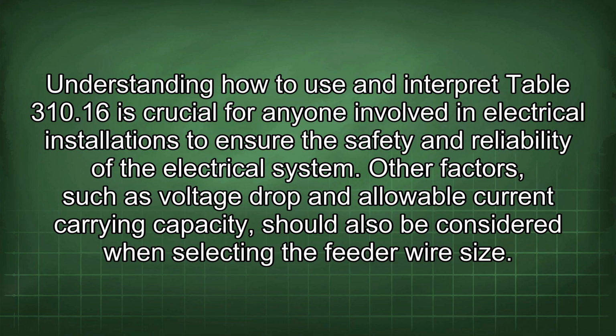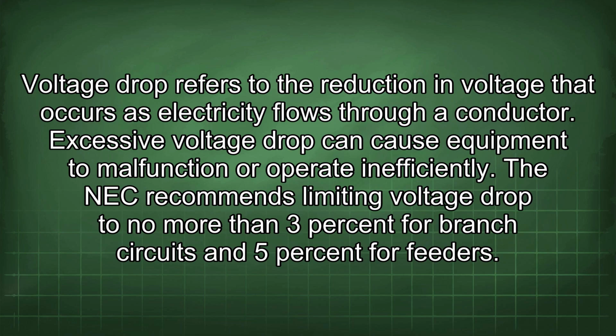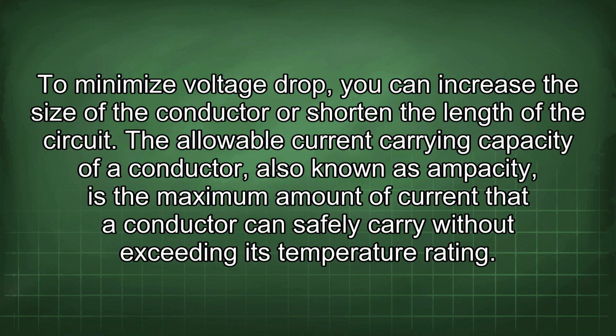Other factors, such as voltage drop and allowable current carrying capacity, should also be considered when selecting the feeder wire size. Voltage drop refers to the reduction in voltage that occurs as electricity flows through a conductor. Excessive voltage drop can cause equipment to malfunction or operate inefficiently. The NEC recommends limiting voltage drop to no more than 3% for branch circuits and 5% for feeders. To minimize voltage drop, you can increase the size of the conductor or shorten the length of the circuit.